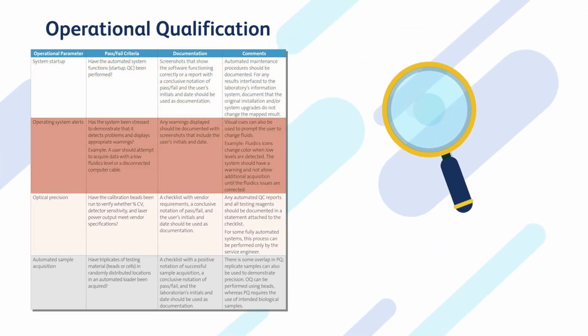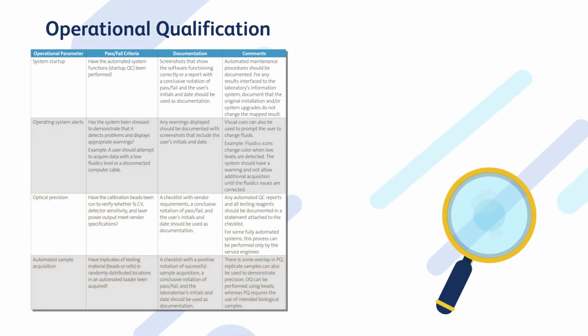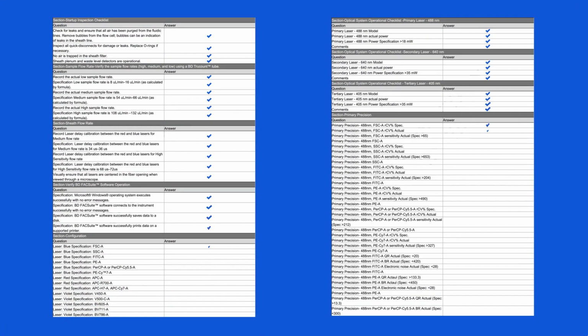During the OQ phase, instrument function is verified against manufacturer specifications and user requirements. A BD field service engineer will perform an operational qualification to measure readiness. Cytometer performance is assessed through various measurement parameters.